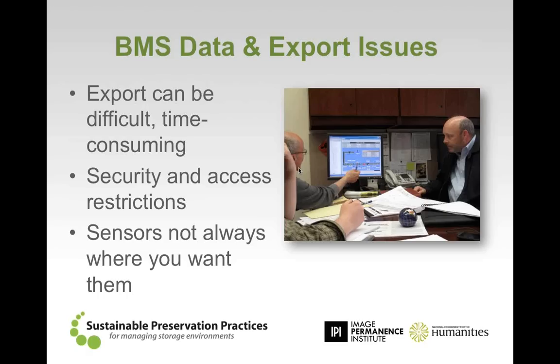And you also have to make sure your system can trend. Most systems can, but there are a few out there that are not capable of trending data. Security and access can be an issue with these systems as well. I came from a background in facility management, and one thing I can say for sure is that you don't want to give access to just anybody. One of my rookie errors was to provide access to somebody who, when examining the system, accidentally shut my cooling tower down in the middle of July, which meant I had no way to supply chilled water to the facility, and it was in the middle of a very hot July. It took me 3 days to solve that.